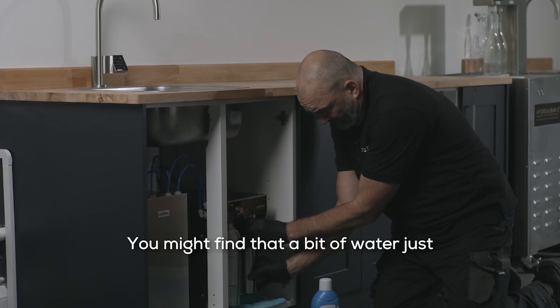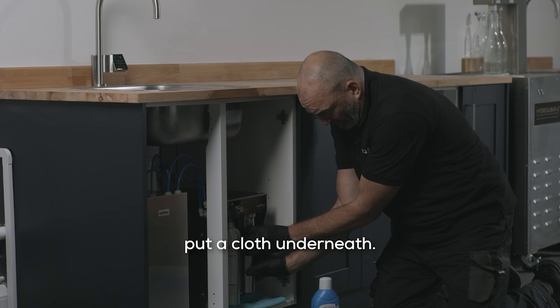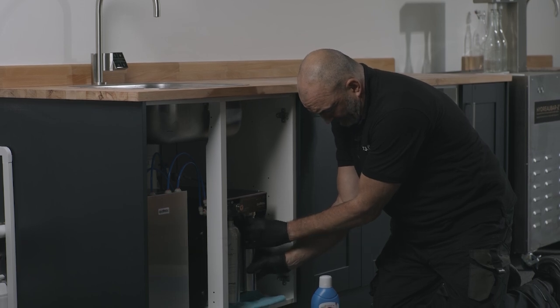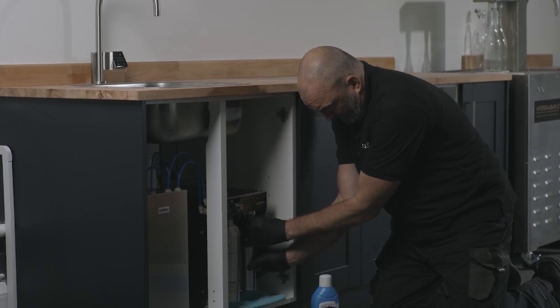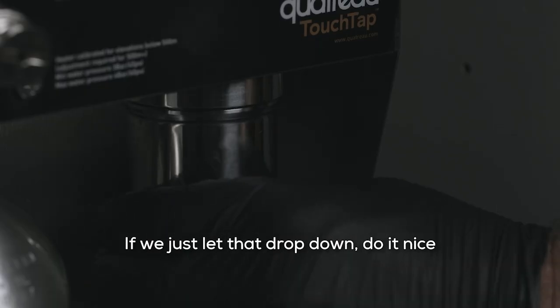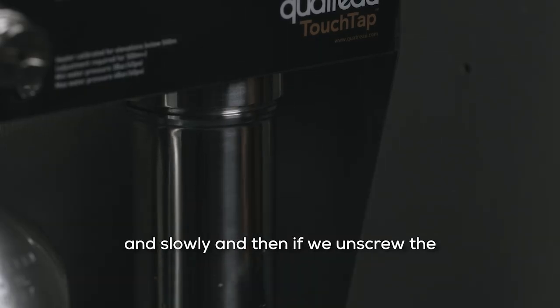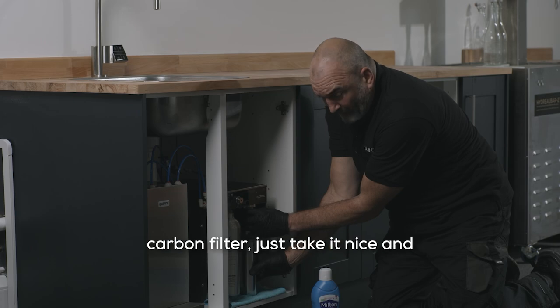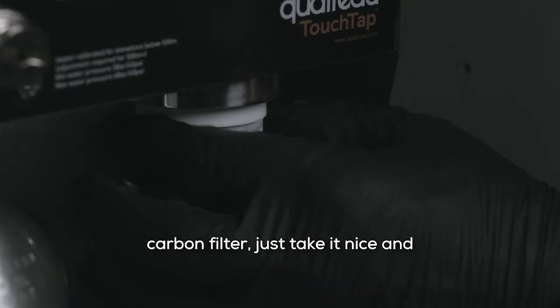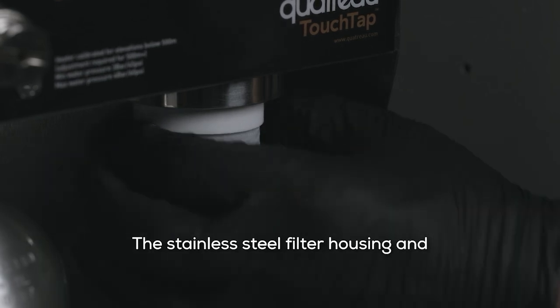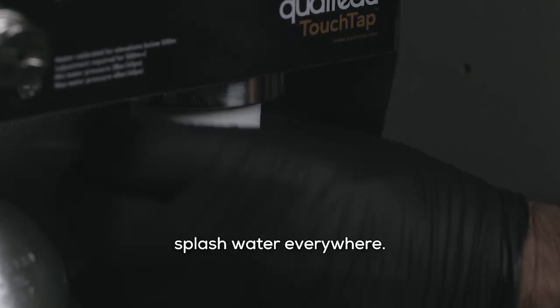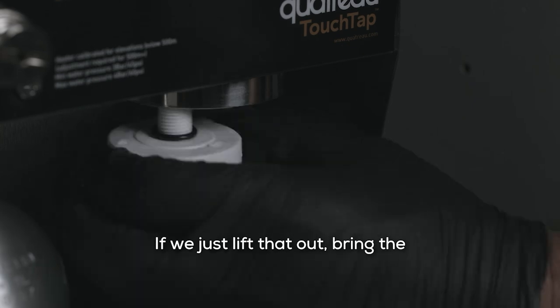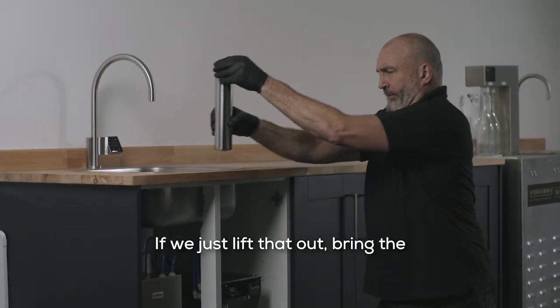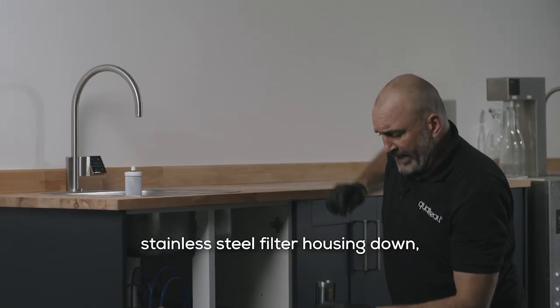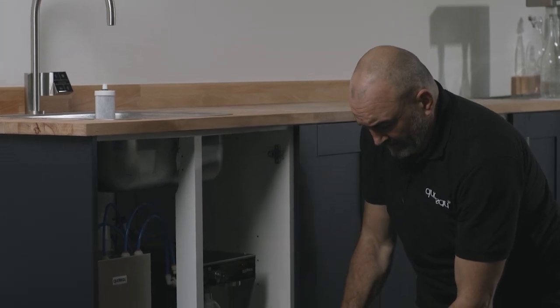You might find that a bit of water just drips out, so as I say, put a cloth underneath. If we just let that drop down, do it nice and slowly, and then if we unscrew the carbon filter, just take it nice and steady, just so that it doesn't drop down inside the canister, the stainless steel filter housing, and splash water everywhere. And if we just lift that out, bring the stainless steel filter housing down, there's still some water in there.